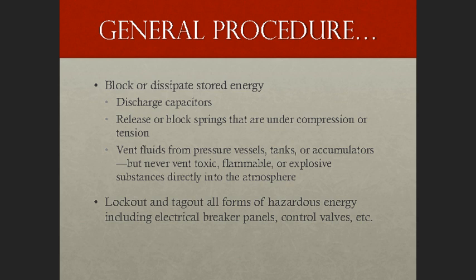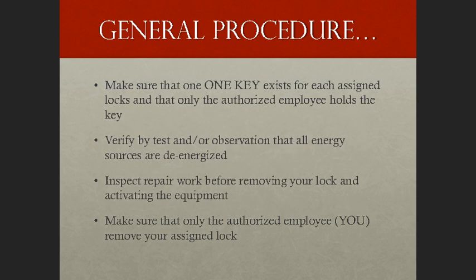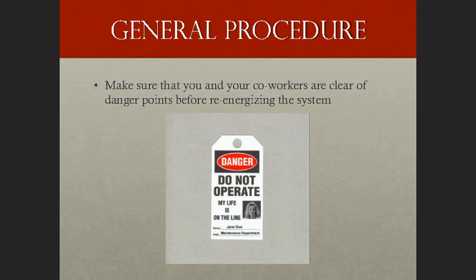The third step is to lockout and tagout all forms of hazardous energy, including electrical breaker panels, control valves, etc. Next, ensure that only one key exists for each assigned lock and that only the authorized employee holds that key. Then verify by test and/or observation that all energy sources have been de-energized. Inspect repair work before removing the lock and activating any equipment. Finally, only the authorized employee should remove their assigned lock, and ensure that all workers are clear of danger points before re-energizing the system.